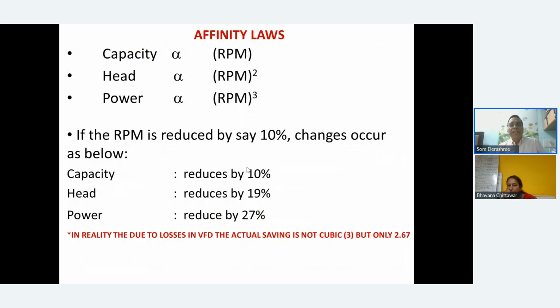Now, what is the affinity law? In all centrifugal machines, whether pumps or fans or blowers, capacity is proportional to RPM, head is proportional to RPM square, and power is proportional to RPM cube. If the RPM is reduced by 10%, the changes occur as below. Capacity is reduced by 10% because it is directly proportional to RPM. Head will be reduced by 19%, and power will be reduced by 27%.